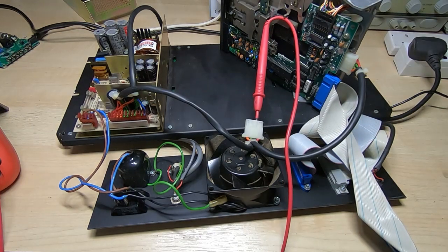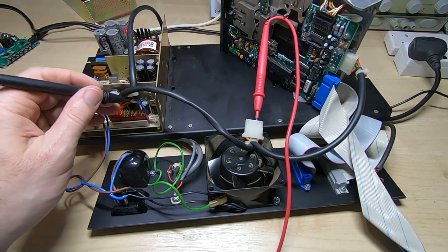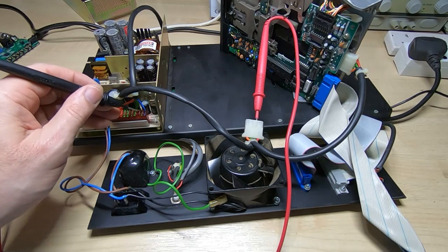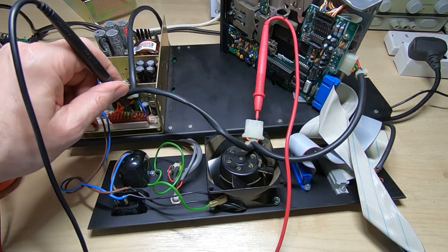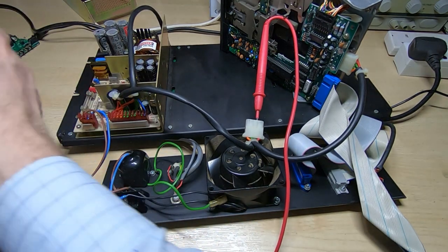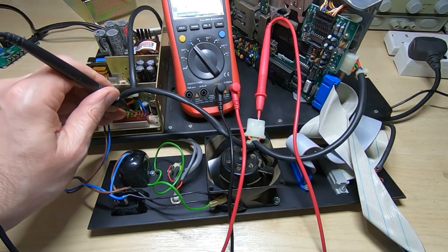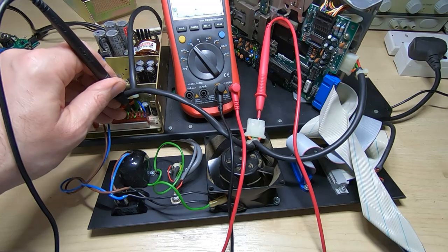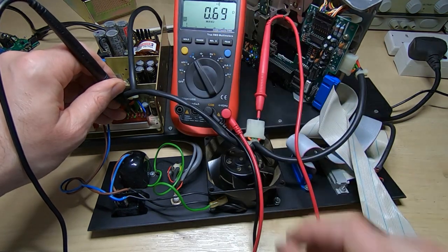And now if we test the same ground lead that I tested before, which is the 4th connection from the end, 1, 2, 3, 4, we're now getting continuity. So that's a dead short, and so we're getting ground. I don't know if you can see the meter there.